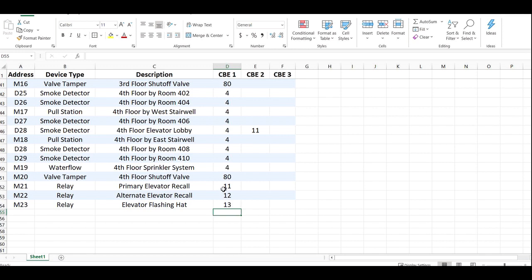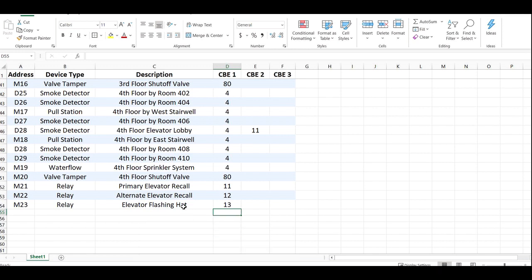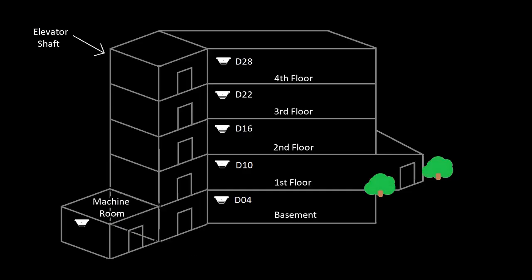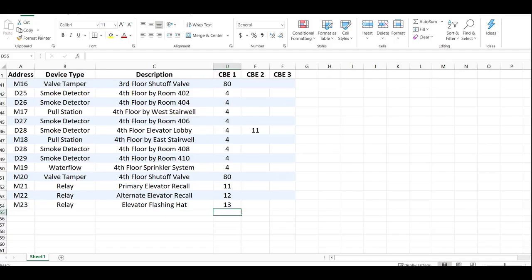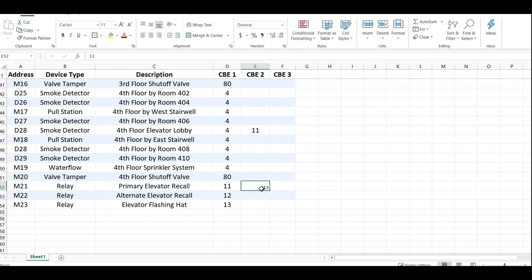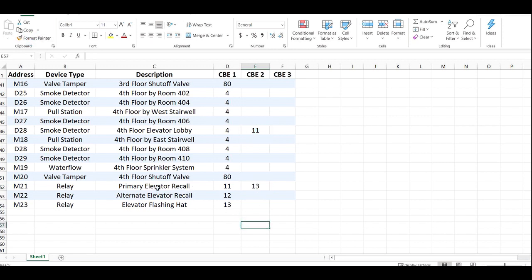But then based on the building, we're going to need to know from the elevator guy: do you want two relays to fire? Because if he tells you 'yeah, I need two signals from you, I need the primary to tell it where to go,' and then in this building we decide, okay well because the machine room's in the basement we're going to send it to the primary floor, then in this instance that's when we go here and put 13 in that column as well. So the primary - when is this relay going to turn on? Well it's going to turn on for 11, or it's going to turn on for 13. So every time the flashing hat triggers, it's going to send the car to the first floor.